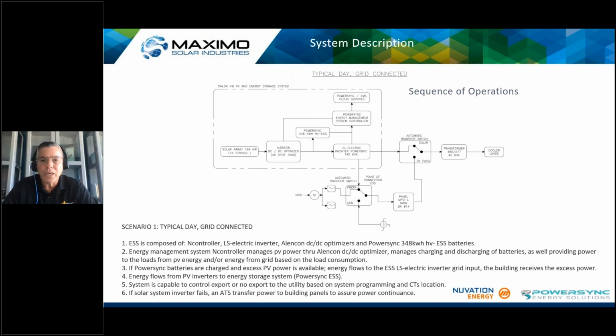One of the important aspects of this design is that the customer required that in case the inverter or the system fails, they're able to transfer automatically to the loads of the building and continue operation through their generators. So we are able to not only assure the backup power, but in the event that 100% of the battery gets depleted, we can still power the loads with the building, and the EMS system from Nuvation is able to know the information and make decisions right there. Next slide.